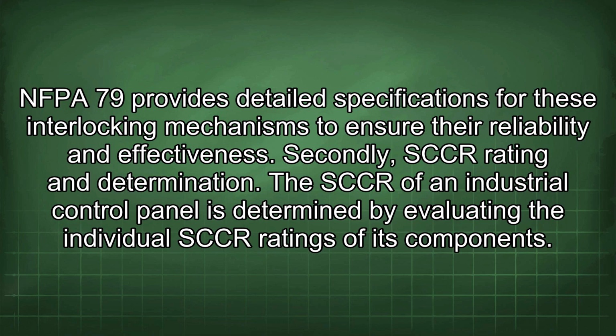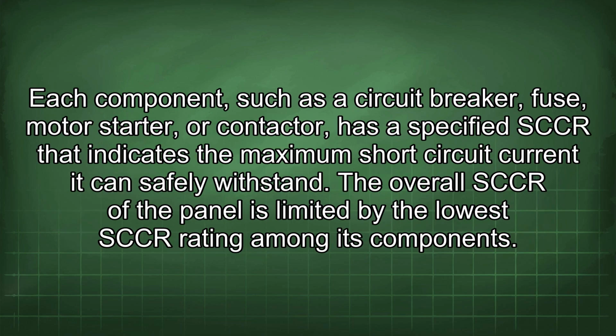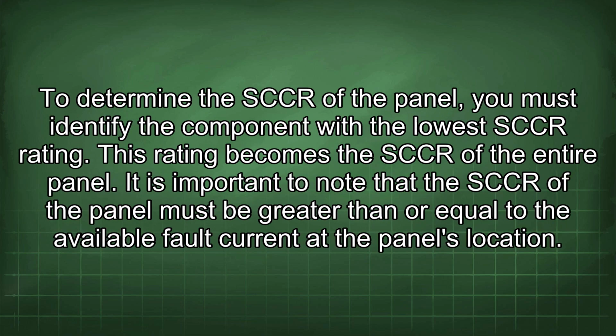Secondly, SCCR rating and determination. The SCCR of an industrial control panel is determined by evaluating the individual SCCR ratings of its components. Each component, such as a circuit breaker, fuse, motor starter, or contactor, has a specified SCCR that indicates the maximum short-circuit current it can safely withstand. The overall SCCR of the panel is limited by the lowest SCCR rating among its components. To determine the SCCR of the panel, you must identify the component with the lowest SCCR rating. This rating becomes the SCCR of the entire panel.